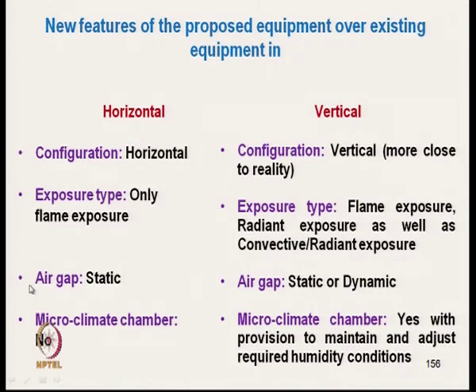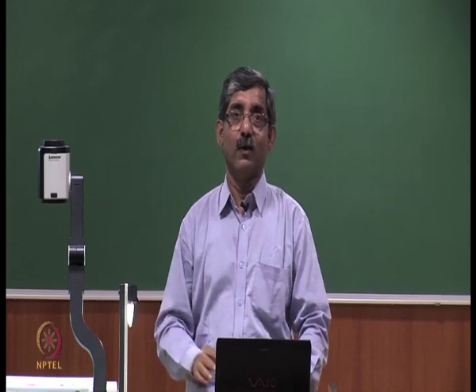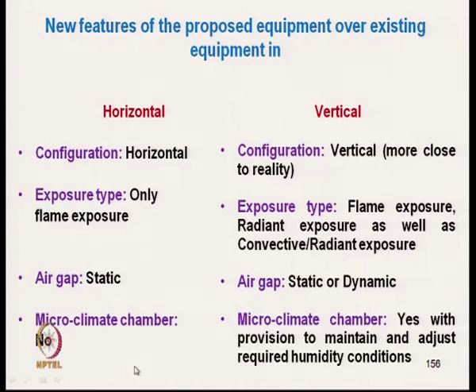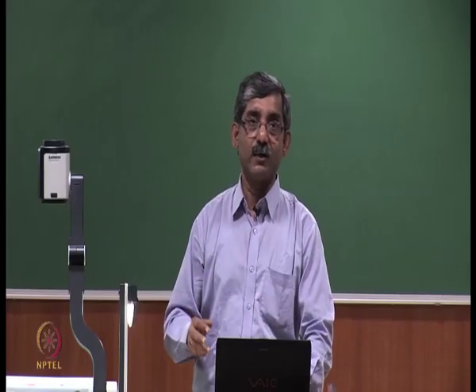In horizontal mode, the air gap was static with no change. In the vertical test, the air gap can be kept static or changed to different levels dynamically. A microclimate chamber, which was absent in horizontal condition, is present in the vertical exposure test and allows adjustable humidity conditions. Let us look at the basic structure of this instrument.